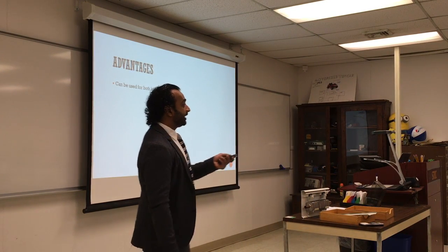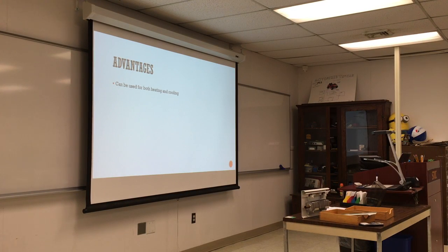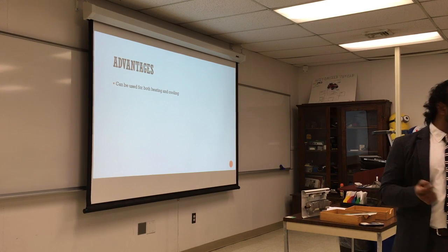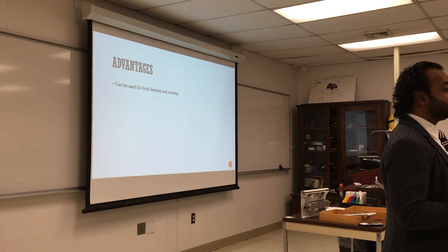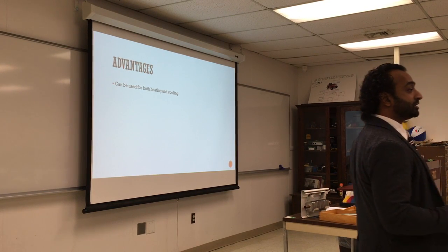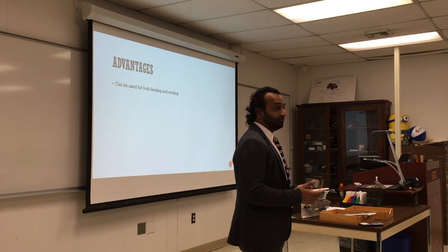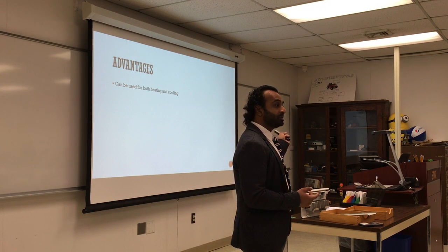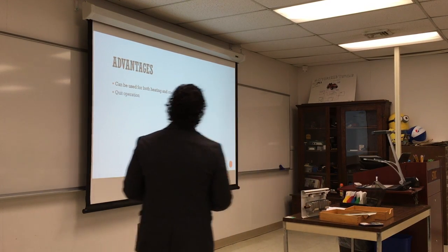So if you look at this thermostat, it can have gas as backup, and you can turn on the gas in January and February. You can have a control that says if the temperature outside is below 40, use emergency heat, which is the gas, so it will turn on the furnace. That's why the controls for furnaces and forced air are kind of involved. If you look at the controls on the Goodman furnace we have, it has more control because you have more options.